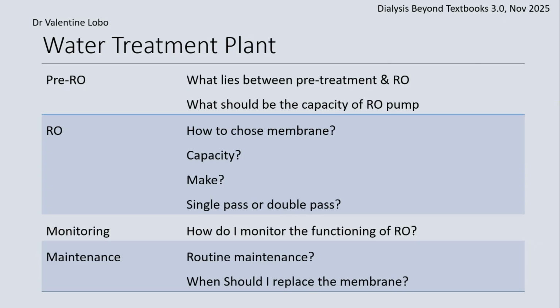And there are pressure switches placed, a low pressure switch before the pump and a high pressure switch after the membranes, which will ensure that the pump would cut off in such situations. So we can discuss RO and its maintenance. Yeah. So how to choose the membrane? Can you show the, yeah.